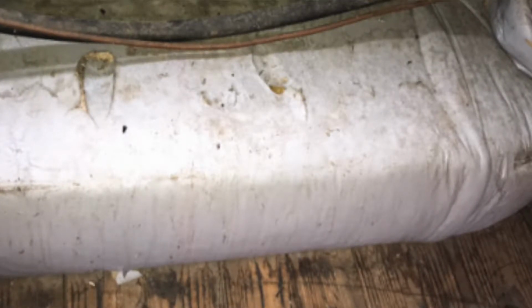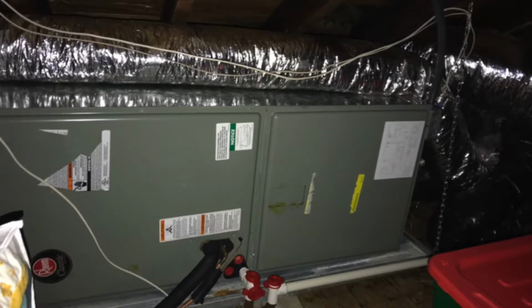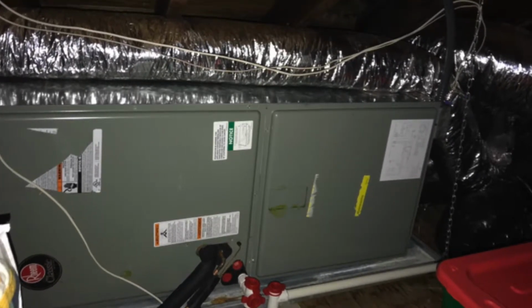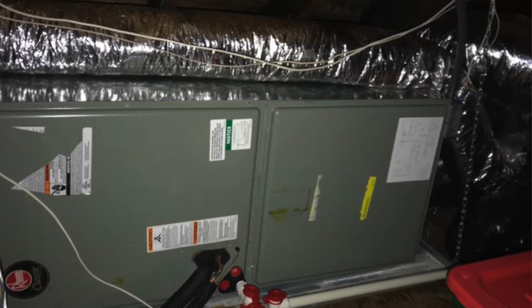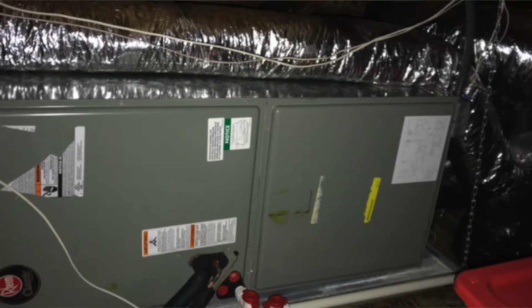Another issue we see in attic spaces with HVAC systems is how the machine is laid. It's really important that if it's laid on its side, it's properly pitched so that when condensation around the A coils naturally occurs, there's a place for that moisture to drain out of the HVAC machine and out of the house.